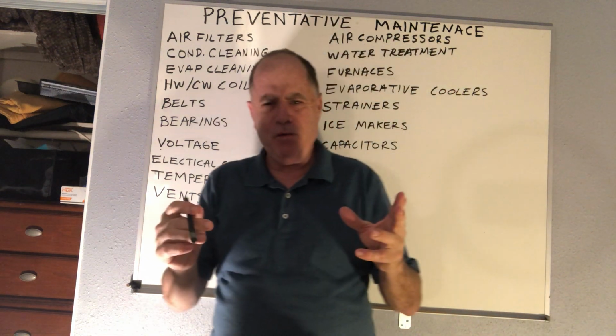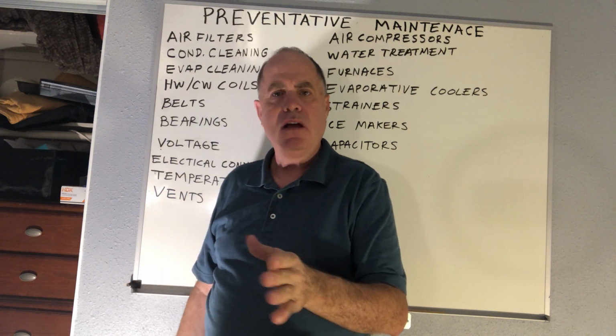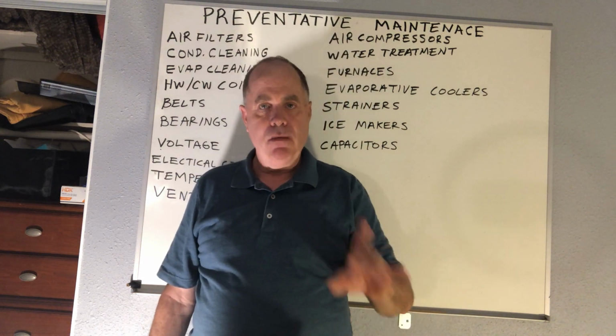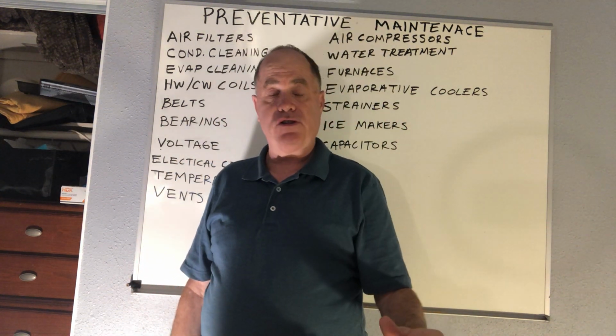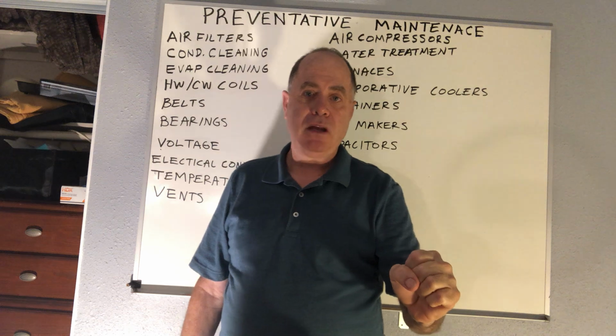Most people in their homes, for your average residential home, if you clean or change the air filter every 6 months, that would be adequate. Now, if you have a lot of carpeting and pets indoors, yes, you may need to replace your air filter more often than that. In this country, we waste millions of dollars every year changing air filters that don't need to be changed. If you ever get in charge of a preventative maintenance program, I want you to remember that.